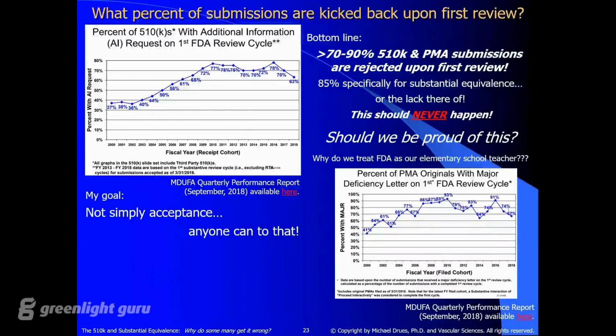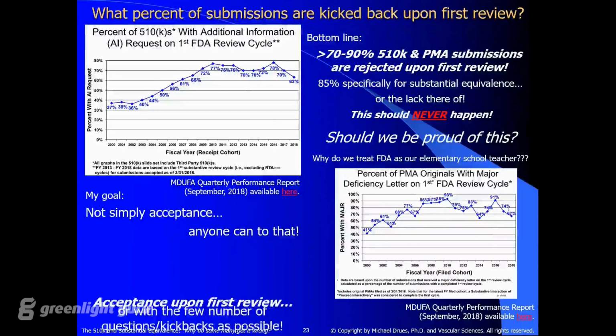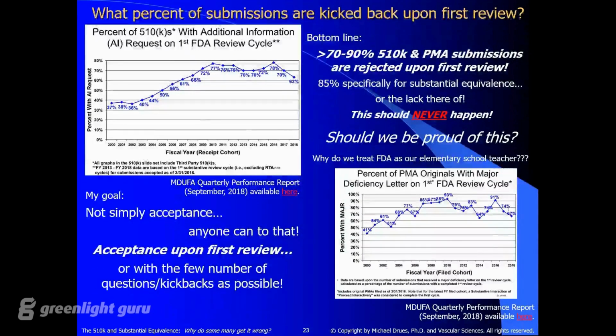Oftentimes I hear my regulatory friends say their goal is to get their 510K cleared, or their de novo granted, or their PMA approved. That has never been my goal, because quite frankly, any monkey can do that. My goal is to get my 510K cleared, ideally first time out of the box if I can. If I can't, with a minimum number of questions or kickbacks going back and forth. Am I successful 100% of the time? Absolutely not. But I can say that I'm in the 20 to 25%, not the 70 to 75%, and that's something that I am very proud of.